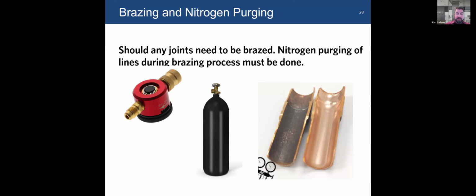This picture on the right is the difference between not using a nitrogen purge and using a nitrogen purge. When the nitrogen is in there, the copper can't react and create copper oxide. There's no oxygen in the pipe, right? That's the point of using nitrogen. They make special regulators for this that allow just a little bit, the slightest whisper of nitrogen, to flow through the piping. If you flow nitrogen through there too fast, you will end up cooling your joint, and then you won't actually get a good joint. You could end up with a cold joint and end up with leaks or a porous joint. So just keep that in mind if doing any brazing.